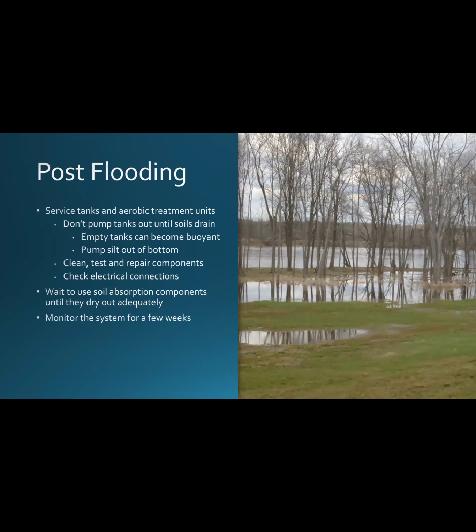So what do we do post flooding? Let's say we've taken our precautions and we are in a flooding situation. We will need to service the tanks and aerobic treatment units. We need to go out there, pump them out and clean them out. We'll inspect them to make sure there's no kind of damage that's been done.